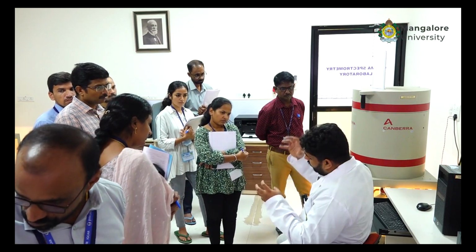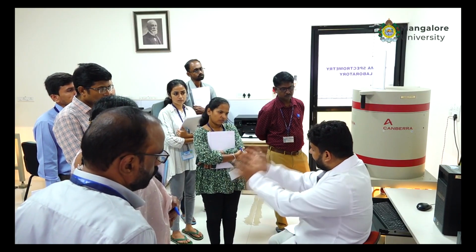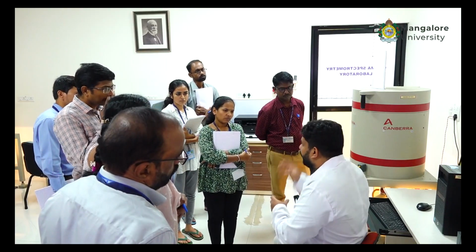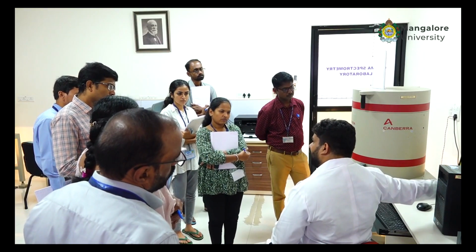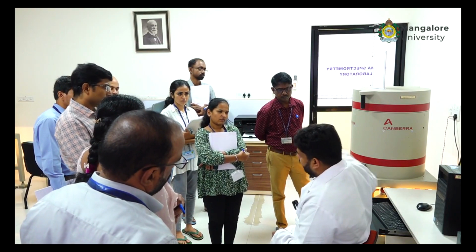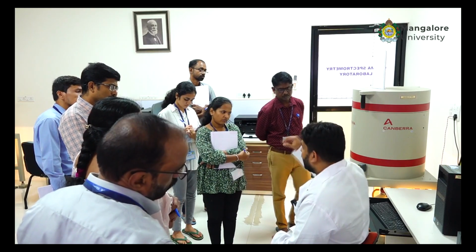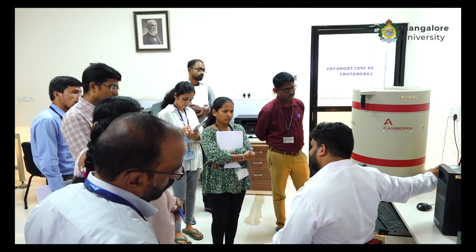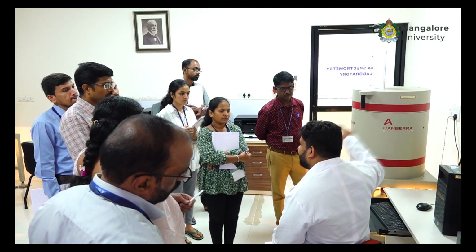They use the same sample, measure it multiple times for years together, and then they say this is the reference material, this is the value. For this peak, for lead-210, this is the value. For uranium, this is the value of this peak. Now I keep this sample, take the count, and using the formula, efficiency is CPS, that is counts per second, times 100 divided by activity, which is the abundance or yield. Since it is in percentage, I get the efficiency of this peak in percent. I'll use that efficiency in later stages to count the samples.